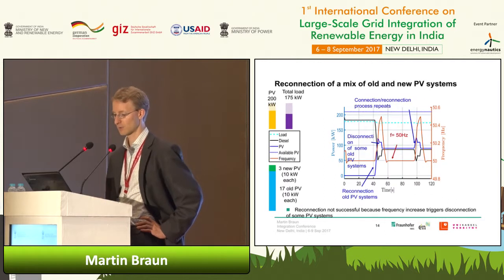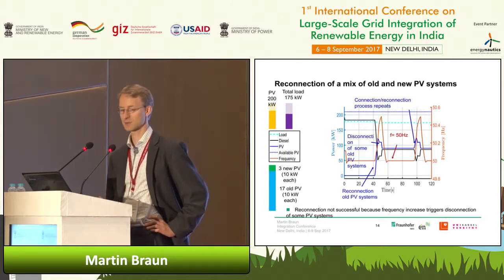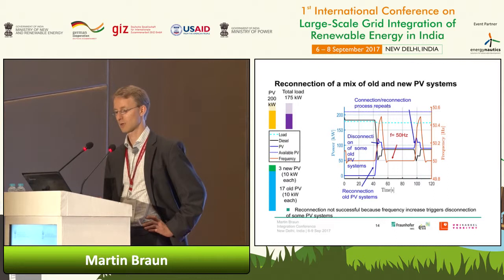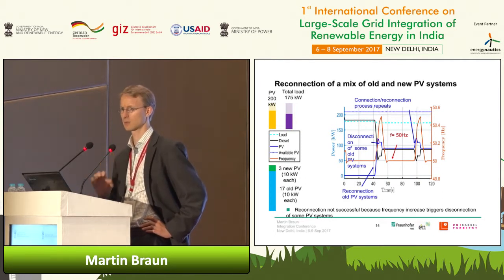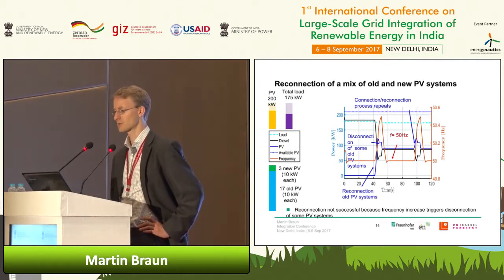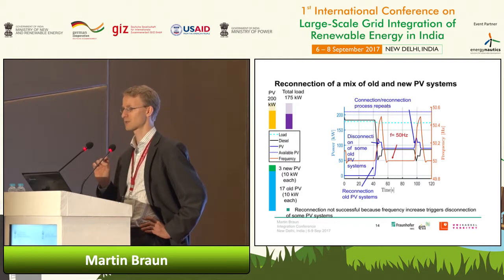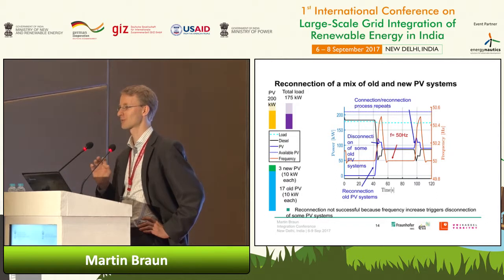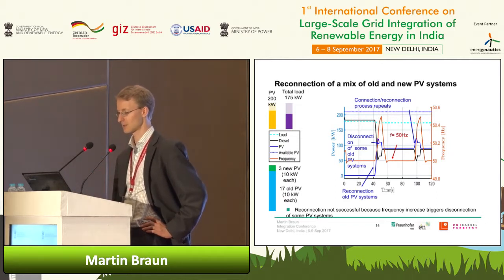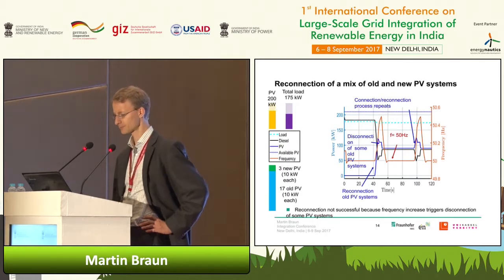But if we have a huge number of old PV systems and only few new PV systems, then we come again into this oscillation mode. So in this simple example, I'd like to give you a clear message that the grid code definition is very important, and you should design it early enough in a way that you can use PV systems in all the different grid conditions in a stabilizing way and not a destabilizing way.